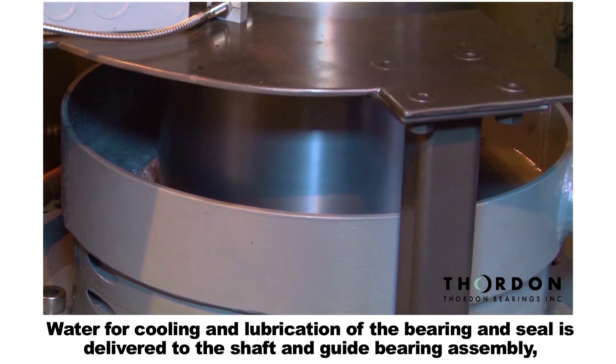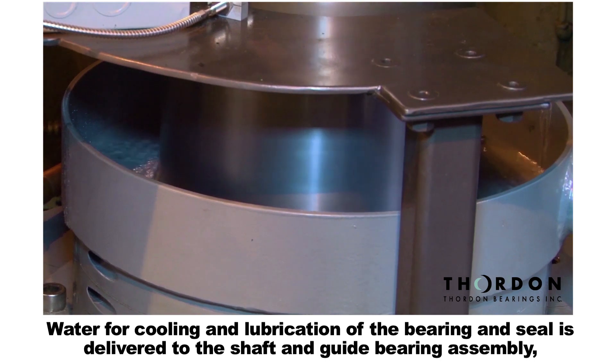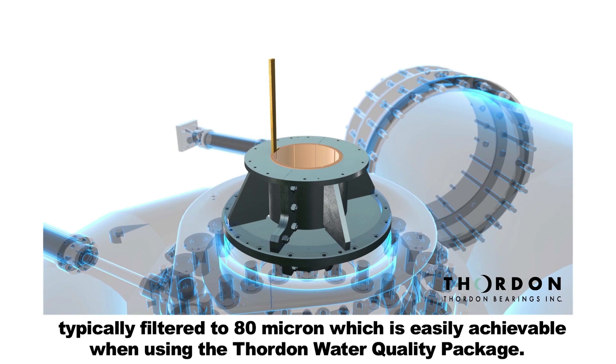Water for cooling and lubrication of the bearing and seal is delivered to the shaft and guide bearing assembly, typically filtered to 80 micron, which is easily achievable when using the Thordon Water Quality Package.